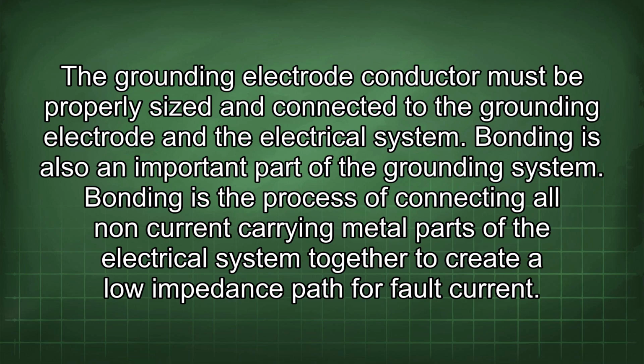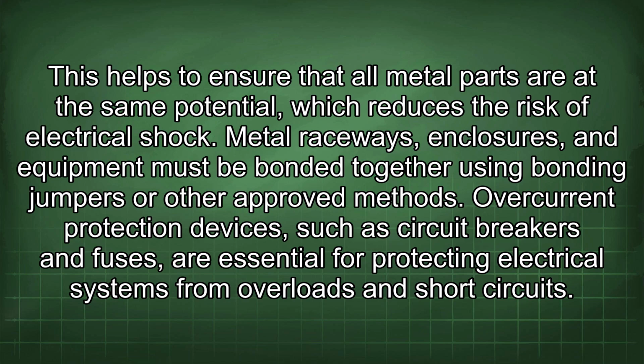Bonding is also an important part of the grounding system. Bonding is the process of connecting all non-current carrying metal parts of the electrical system together to create a low impedance path for fault current. This helps to ensure that all metal parts are at the same potential, which reduces the risk of electrical shock. Metal raceways, enclosures, and equipment must be bonded together using bonding jumpers or other approved methods.